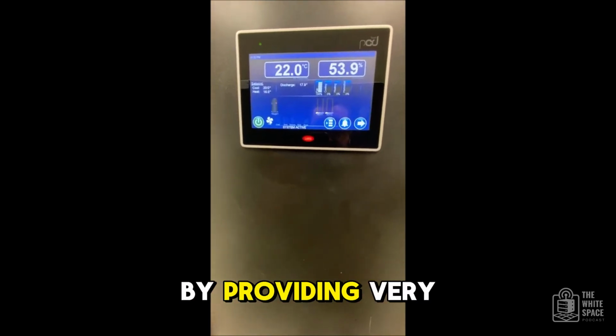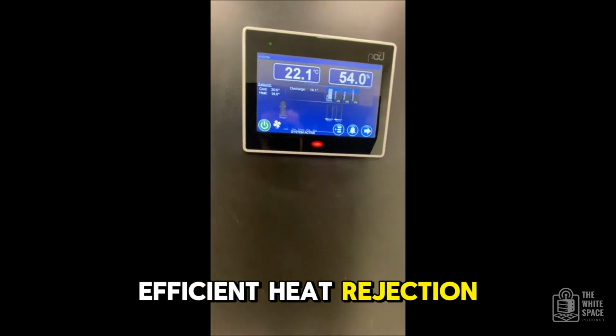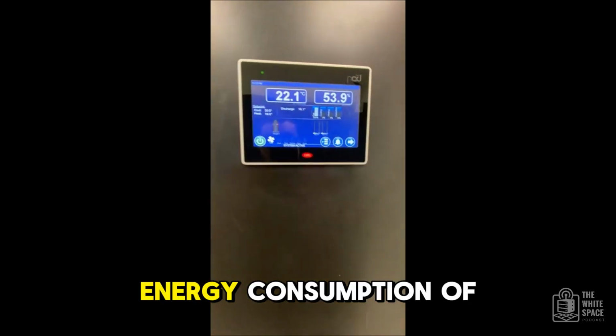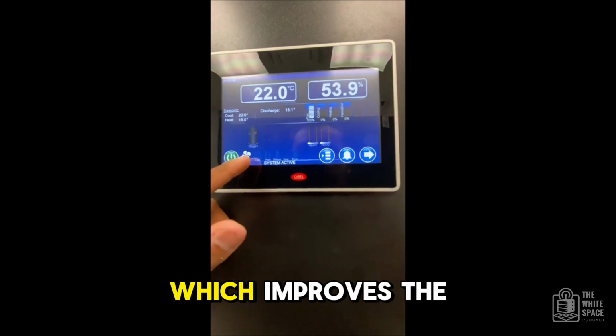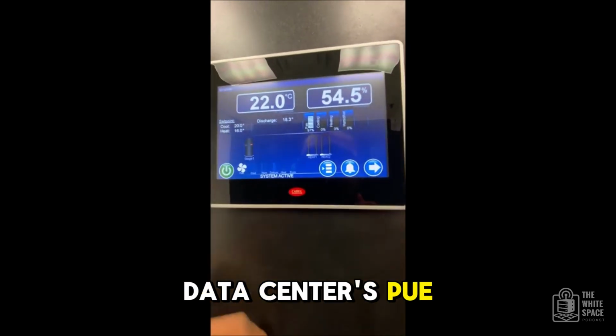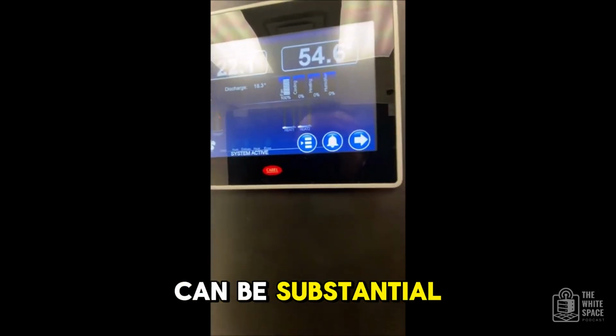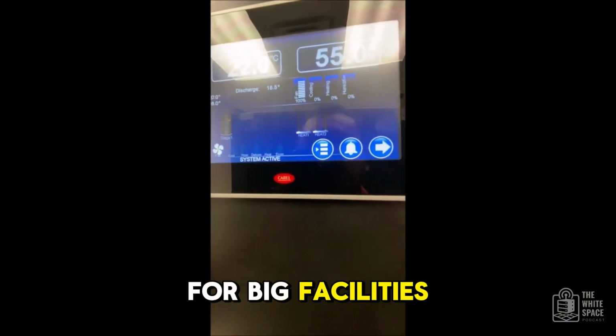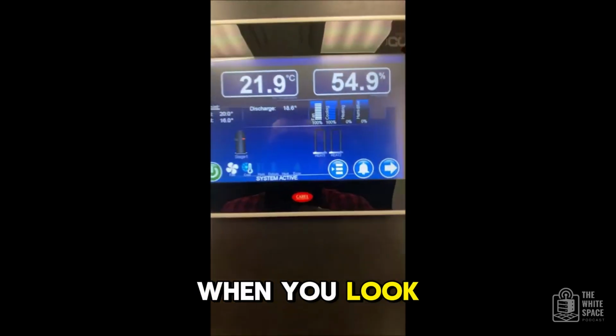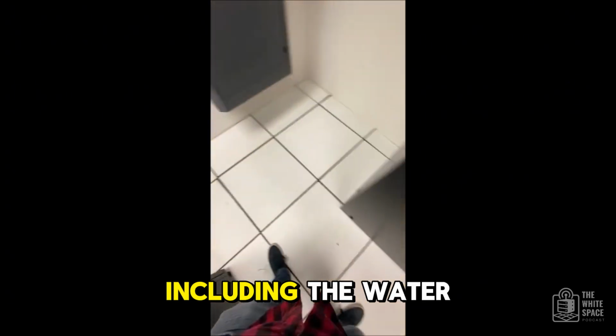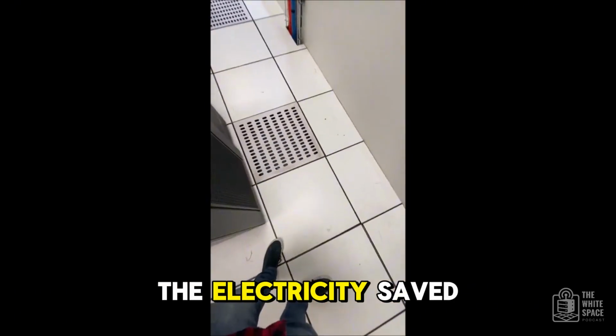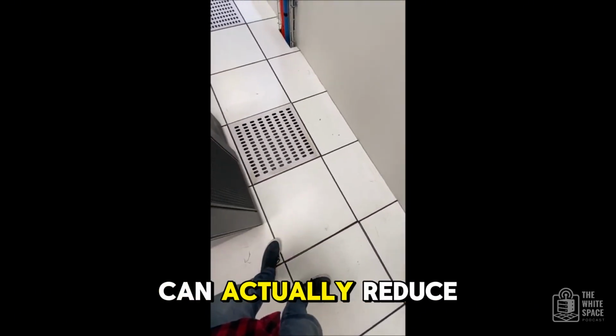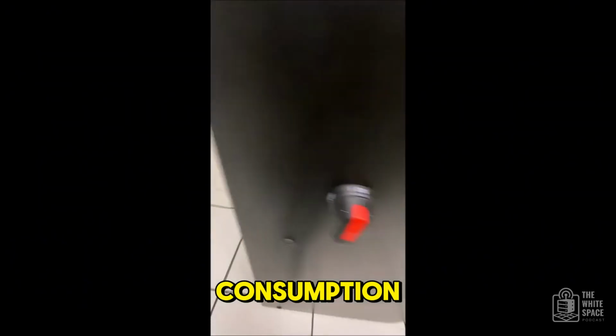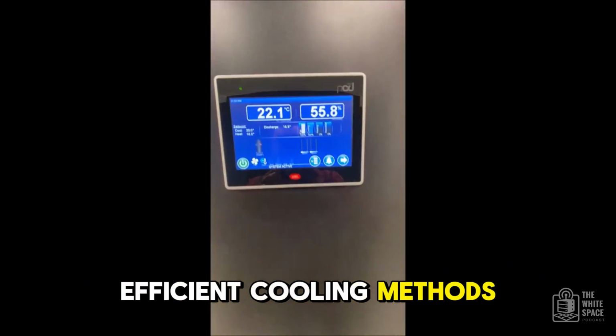Absolutely. By providing very efficient heat rejection, cooling towers help lower the overall energy consumption of the cooling system, which improves the data center's PUE. The energy savings can be substantial, sometimes paying back the tower's cost in just a couple years for big facilities. And it's worth noting, while you see water vapor coming off them, when you look at the total water footprint, including the water used to generate the electricity saved, efficient cooling towers can actually reduce the overall water consumption compared to less efficient cooling methods.